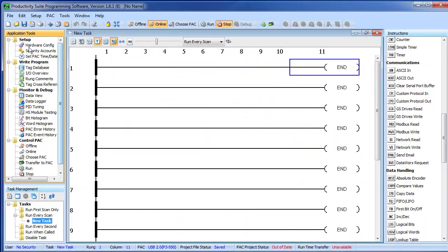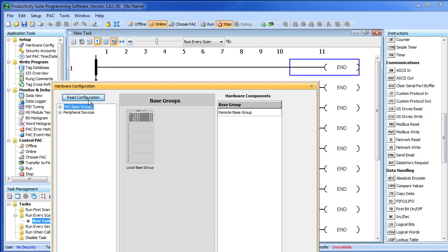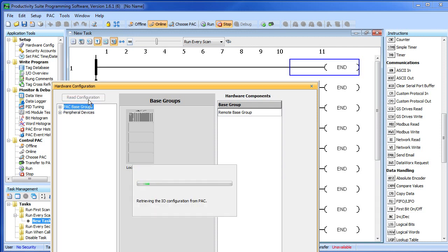To do that we bring up the hardware configuration. We want to read the configuration of the current controller. If this button is not active, check and make sure your controller is in stop mode—it has to be in stop mode in order to read the configuration. I'm going to click on the button and we'll wait a few seconds while the controller does a full auto-discovery of the entire system.